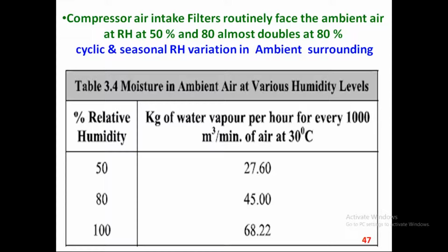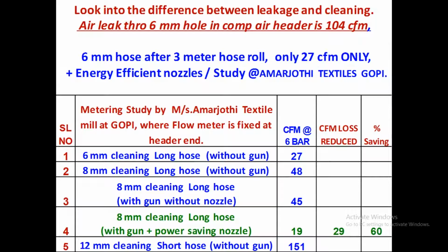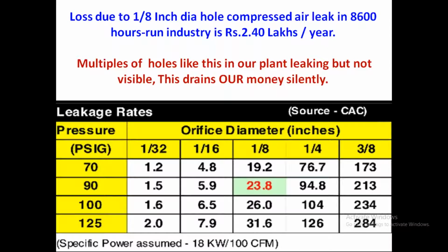So the temperature and the RH for the ambient, from 50 to 100 percent, you can see 27 kg and 68 kg. This is the area, almost 100, it is getting doubled. So the seasonal RH variation between day and night time, and between an inland place and a coastal place, all these aspects take place. Coming to the cleaning aspects, a 6 mm hole leakage straight away goes to 104 CFM. You can see a 1/4 inch, 6 mm hole, almost 104 CFM is getting lost.